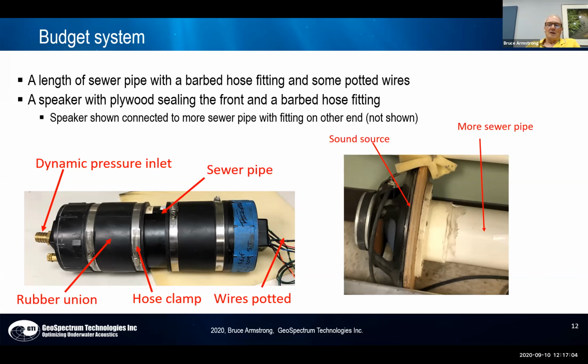And if you take a speaker and put a piece of plywood on the front of it and connect it to the dynamic pressure inlet, now you've got a sound source. So you just take some signal generation, pass it through an audio power amplifier, and drive the speaker. That produces pressure that enters the piece of sewer pipe. And then you've got a perfectly fine calibrator. The only expensive part about this system is the pressure transmitter, which is typically about $1,000.